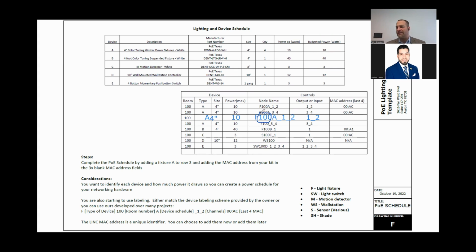I've done that before. I like that. And the fixture number is associated with a room. So you'd say all fixtures in room 100 are 101, 102, 103, or all fixtures in room 110 are 111, 112, 113. And that could be very helpful too. And you could redline the drawings. I've done that. I like that. It's by no means like locked down. This isn't the only way you could do it.